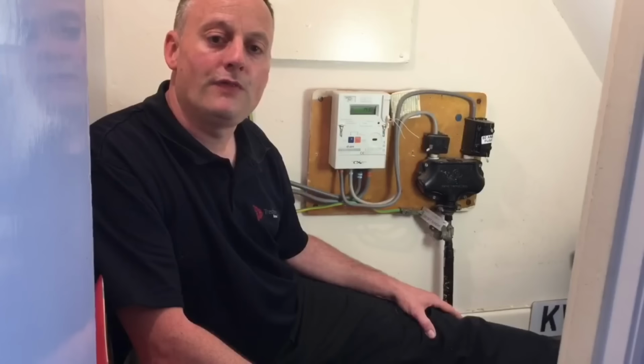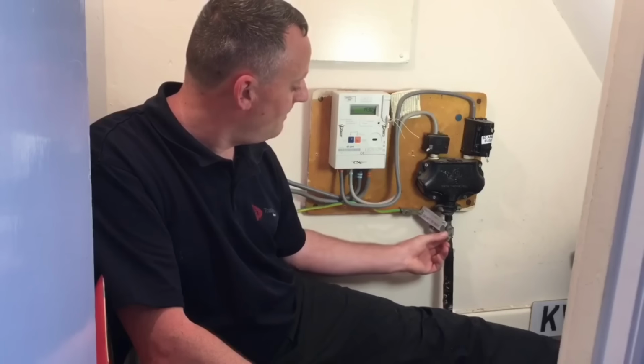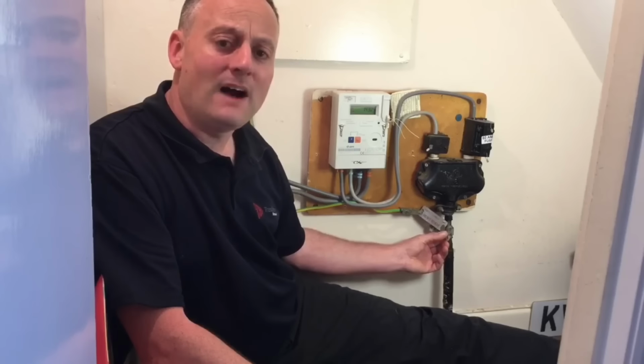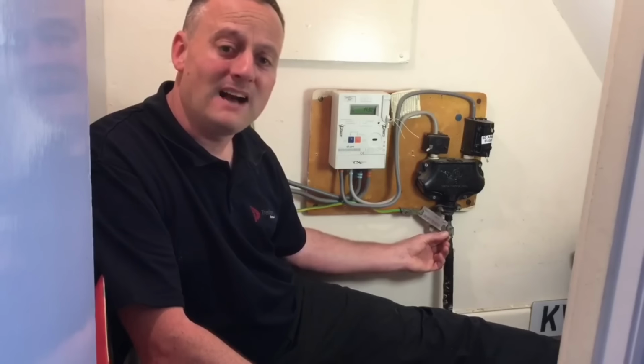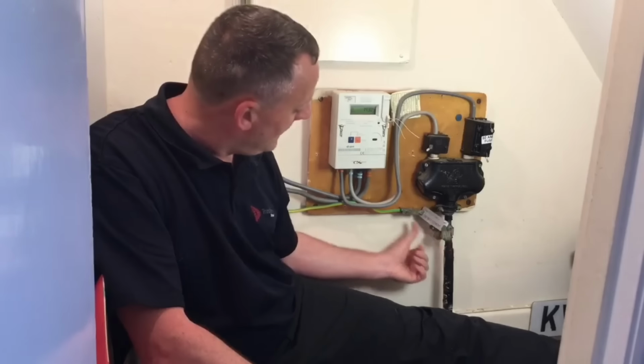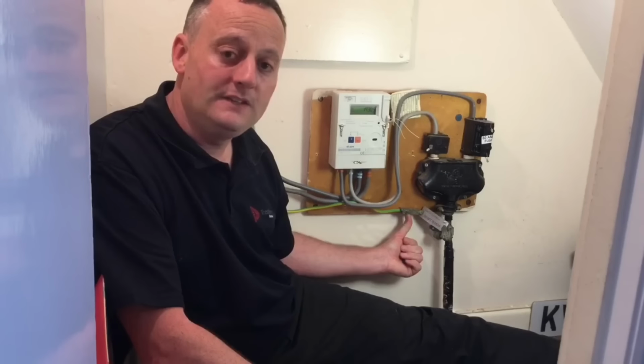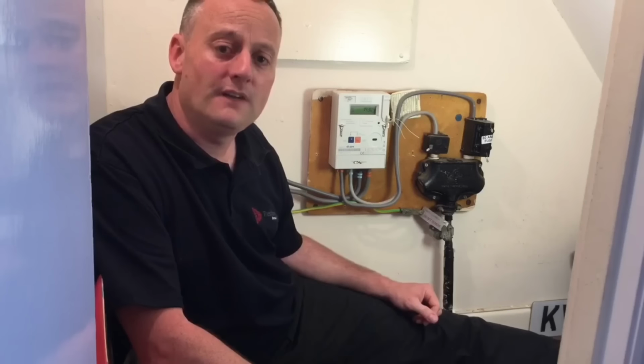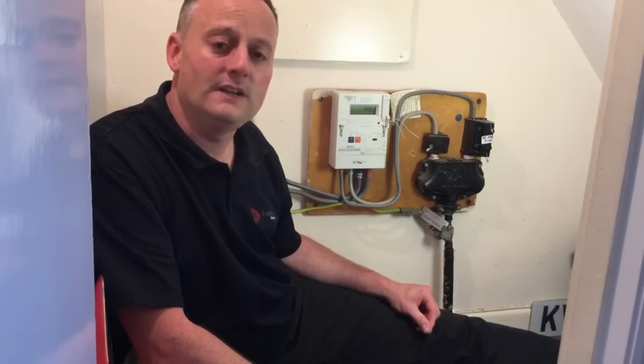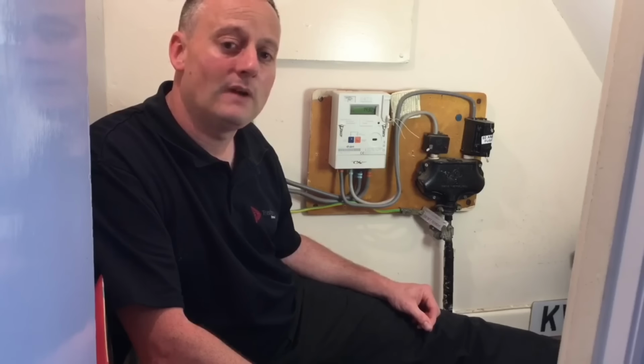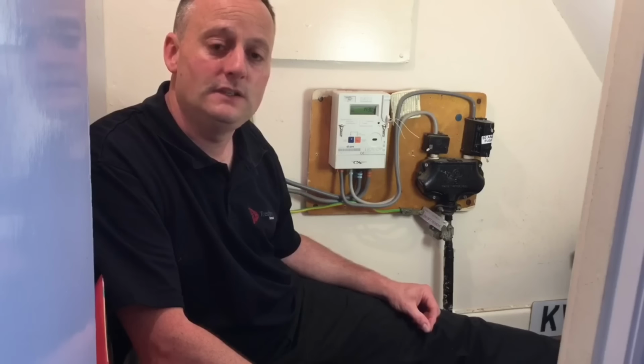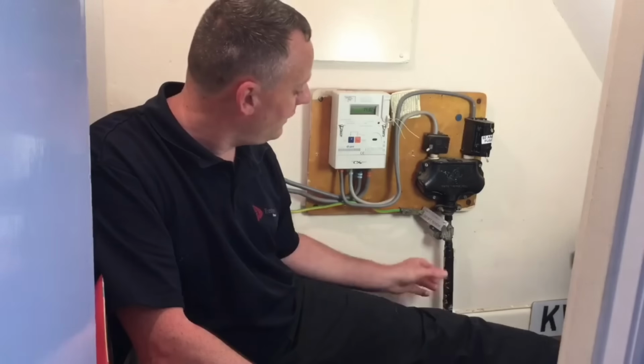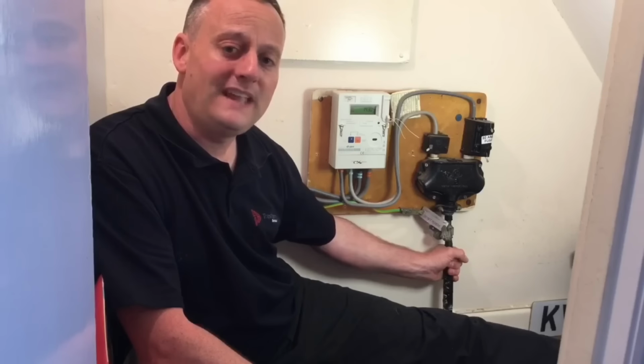So we've got to look at the supply authority's cable incoming to work out the earthing arrangement we've got. We can see this time we have this steel outer sheath being taken from the outside of the supply authority's cable into the MET, the main earthing terminal, and not, as in our previous TNCS earthing arrangement, coming out the same termination point as the neutral. So therefore this earthing arrangement must be different than the one we previously looked at in our video. So we're now looking at an earthing arrangement where it comes off the outer sheath of the supply authority's cable.